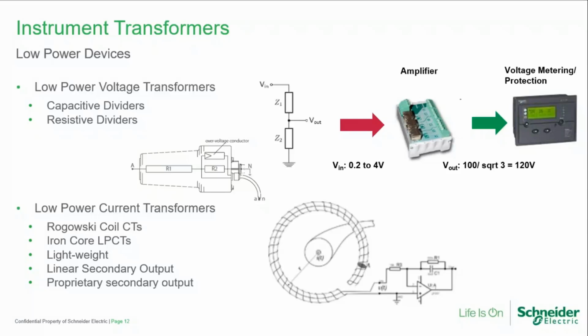Now, the downside right now on the market today is that a lot of these products are proprietary, and they have to be used either with particular styles and manufacturers of meters or particular styles and manufacturers of relays. I have seen low power voltage transformers on the market today that are not proprietary, that can be used with anybody's relays and meters, and they usually involve some type of amplifier system. I have yet to see any low power CTs that are not proprietary. Most of the ones I've seen, or all the ones I've seen on the market today, have to be applied to a specific type of meter or relay. So just keep that in mind if you're looking to use these newer styles of instrument transformers.